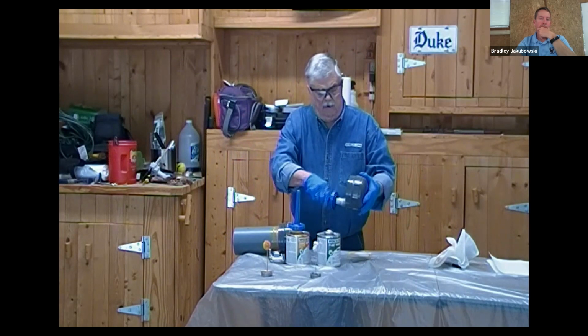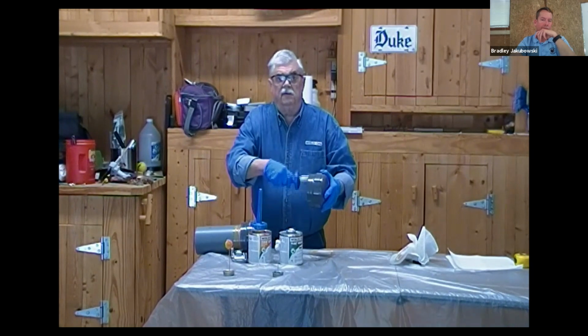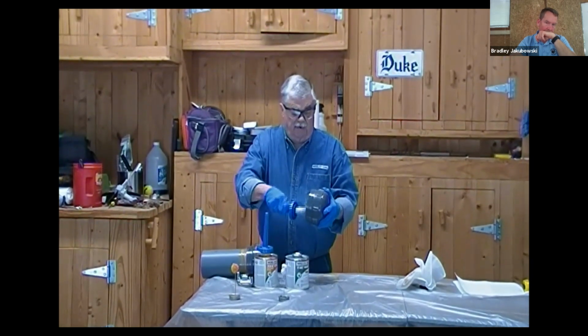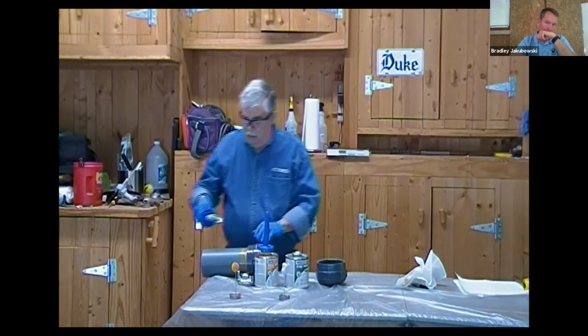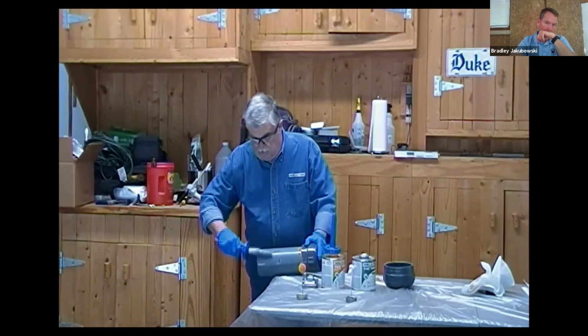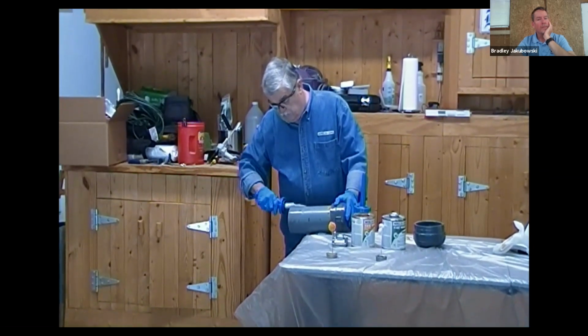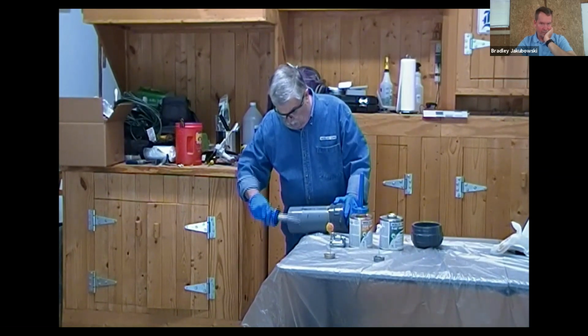First, we're going to prime my cap again and vigorously scrub the cement in. I cannot emphasize that enough. Do not just paint it on. You need to scrub it in until you feel the swab start to drag. That means the plastic is starting to soften up. Okay, satisfied that my piping is properly primed, all the ink markings have disappeared.